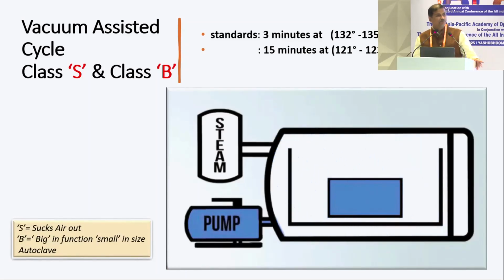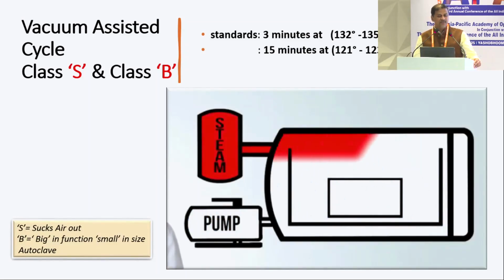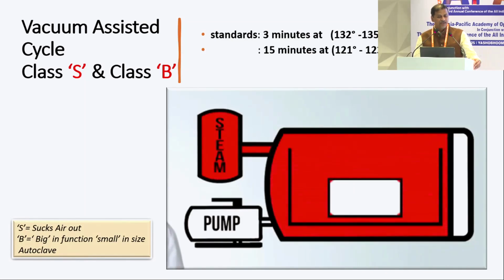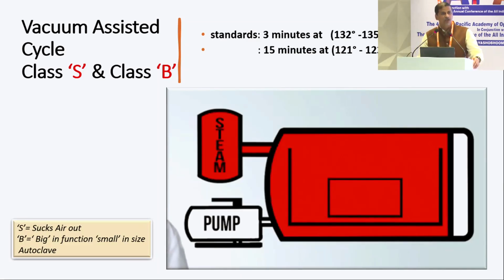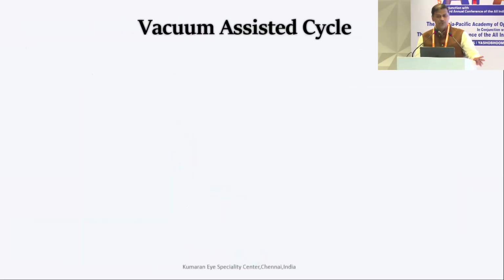Vacuum assisted is of 2 types, class S and class B. Simply, to understand it, class S means it sucks the air out, and B is big in function, and smaller size autoclaves are what we call the B autoclave. So it's very easy for you to keep this mnemonic in mind when you are talking about class S and class B, and there are 2 kinds of temperatures used here.